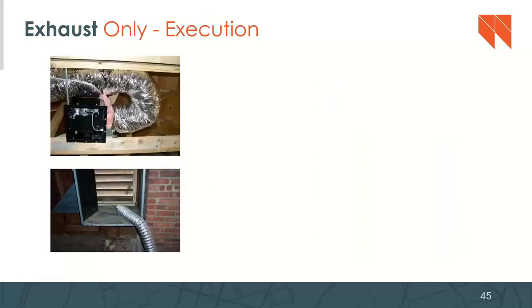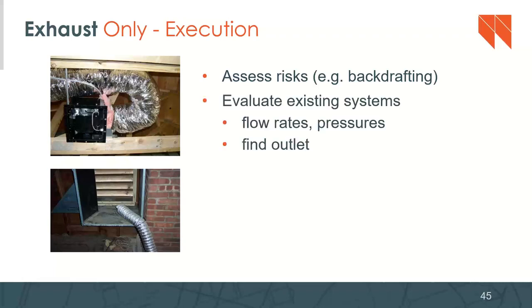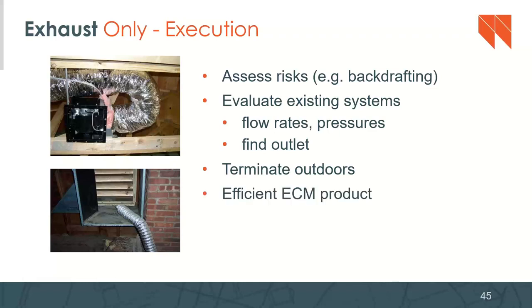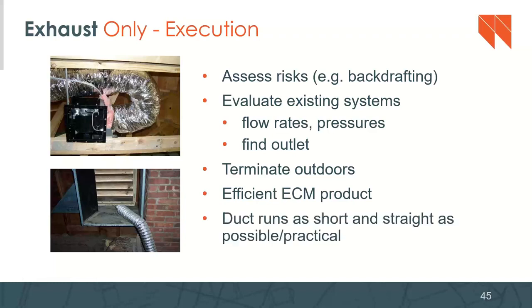So what does exhaust only look like in practice, in execution? You want to assess any risks, in terms of what your design might take into account. If there are any existing systems, you want to evaluate those. So you want to know what the flow rates are, what the static pressures are, and where the outlet is going. You want it to terminate outdoors, and you want an efficient ECM product, an efficient fan that is going to make all of this run. And any duct runs should be as short and as straight as possible and practical.